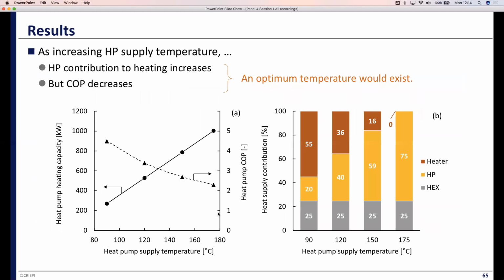From this slide, I will explain the results. The left graph shows the influence of heat pump supply temperature on the heat pump heat supply and the COP. As the heat pump supply temperature increases, the heat pump supply increases, but the COP decreases. So an optimum temperature would exist.